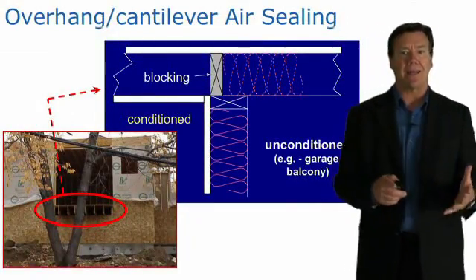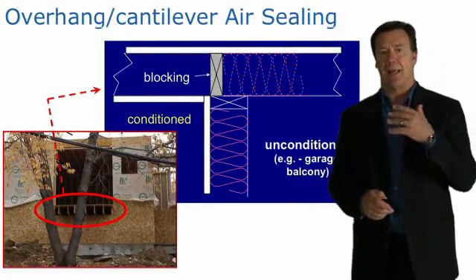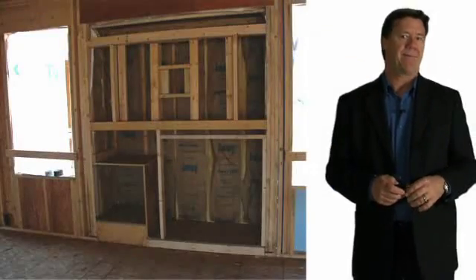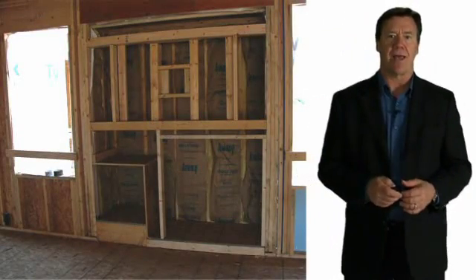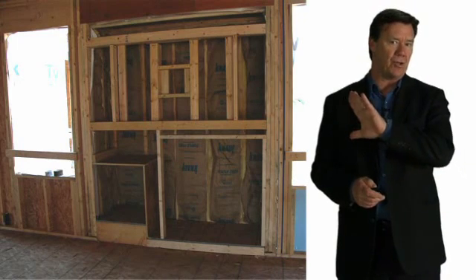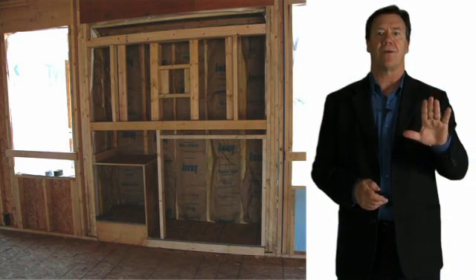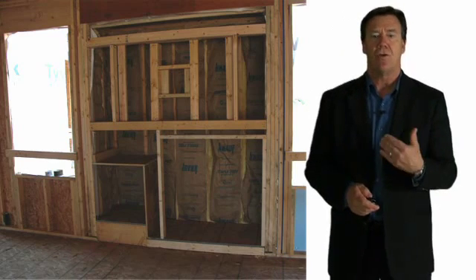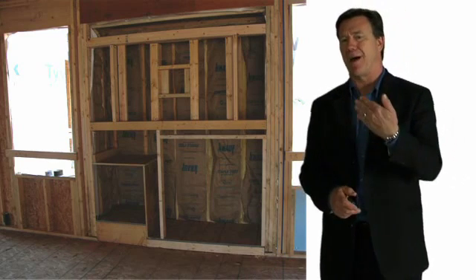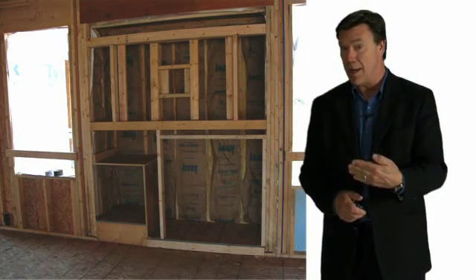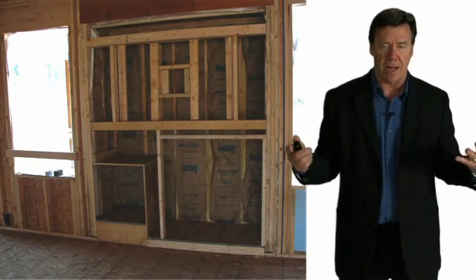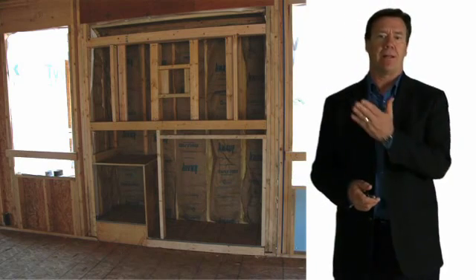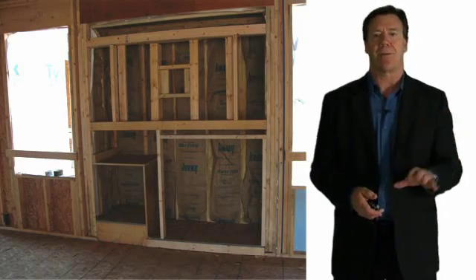Duct penetrations must be foamed and sealed. Cantilever and rim-joist areas need to be air-sealed. For fireplaces, even though gypsum wallboard will cover the location, there's often a lot of hollow space behind it with insulation exposed to air — that cannot be the case. You have to completely put an air barrier around that entire space.